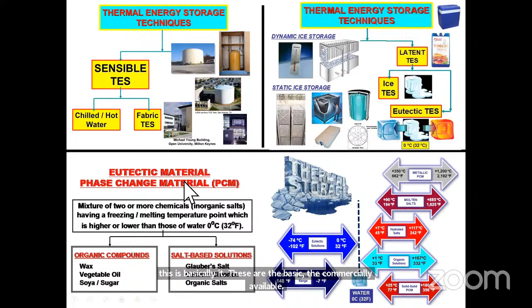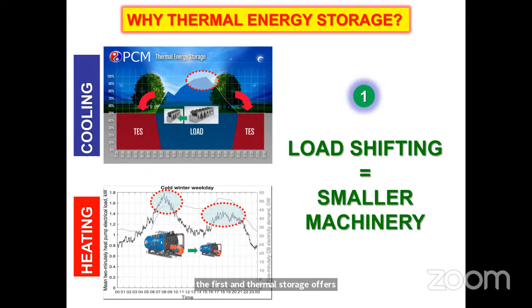In big buildings, you see heating load peaks in the morning and late afternoon when people return, and for air conditioning, the peak is at lunchtime. So you have these mountains to climb. Instead of climbing these mountains, if we shift those peaks to off-peak periods, we can level the load, meaning we need smaller machinery. That's the first advantage thermal storage offers, for both heating and cooling duties.